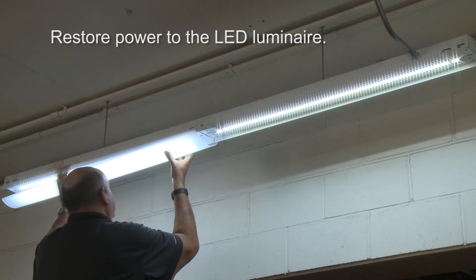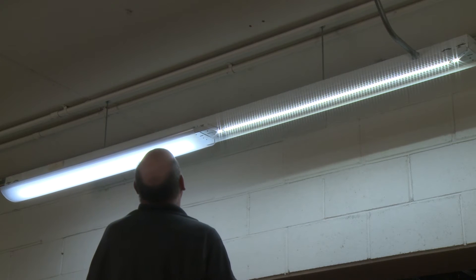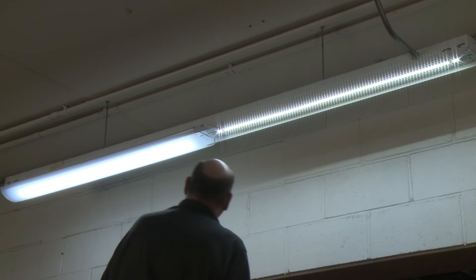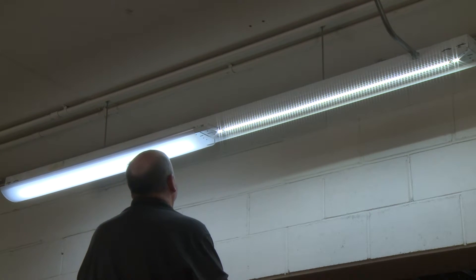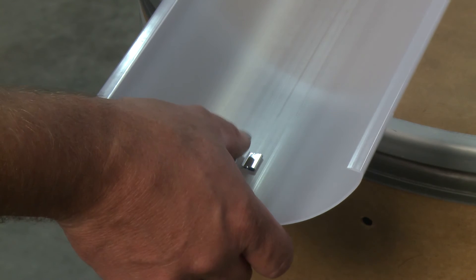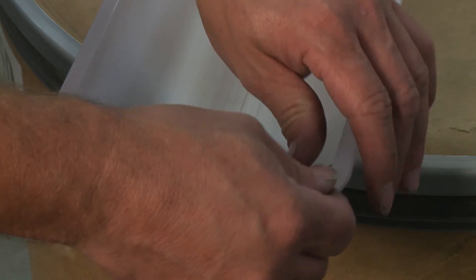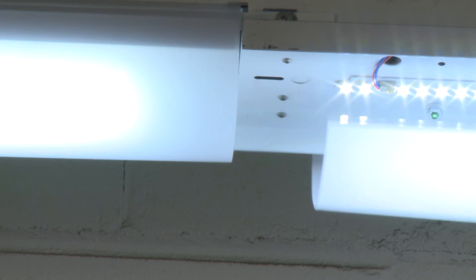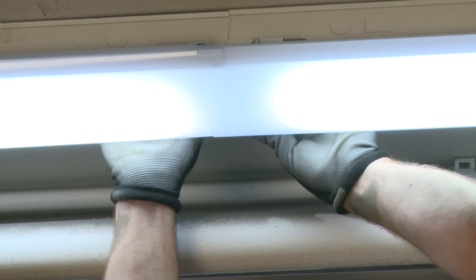Finish off the LED luminaire with the frosted diffuser. This one-piece snap-on, polycarbonate and UV-stabilized diffuser provides even lumen distribution without glare, shadows or hot spots. When retrofitting an eight-foot fixture, the diffusers are connected together using two small clips. Attach two clips to the lip of the diffuser by sliding them on about halfway so that half of the clip is protruding. Then install a second diffuser and butt the two diffusers together so that the second diffuser attaches to the clips on the first diffuser.